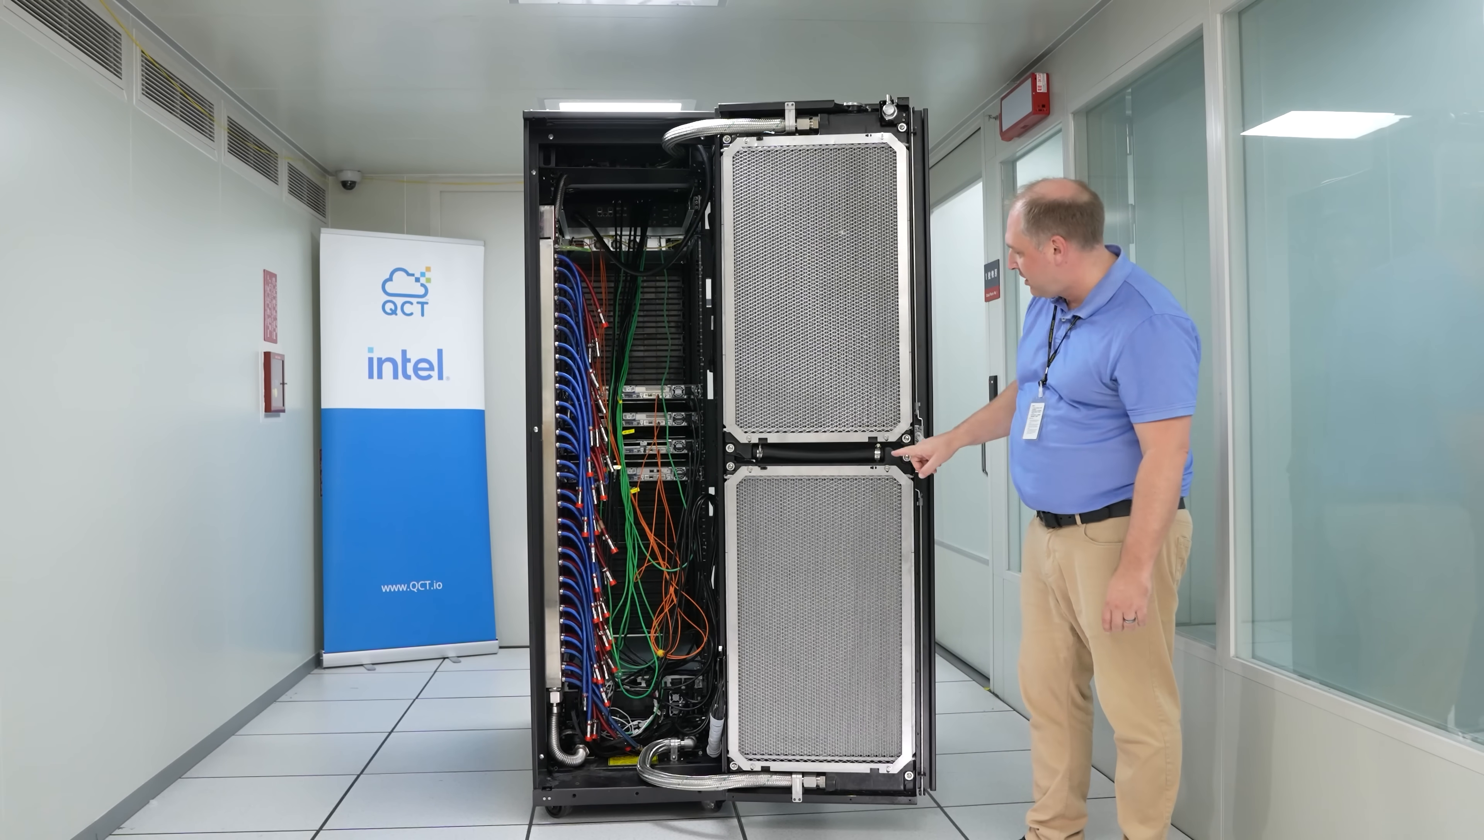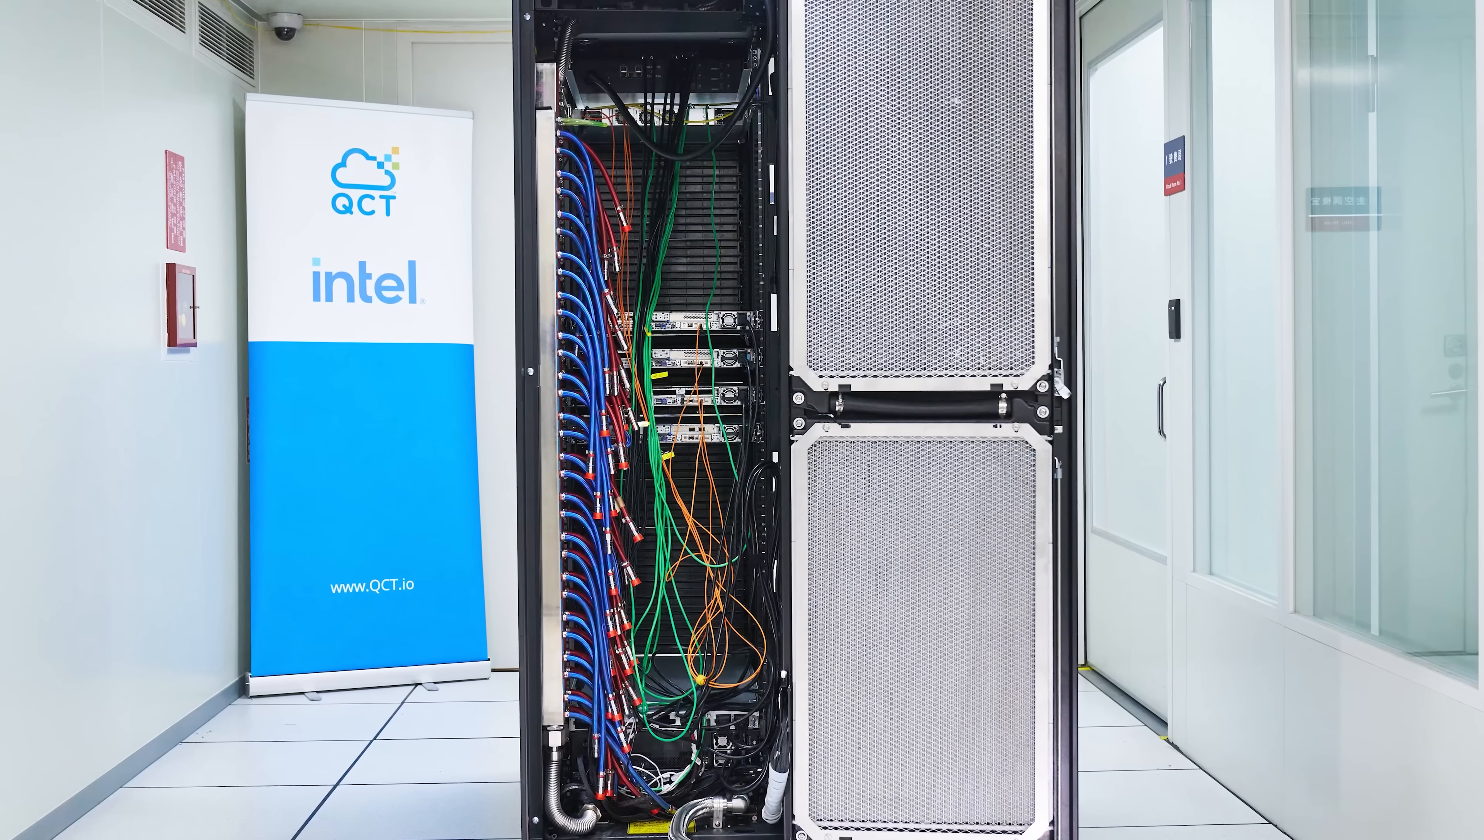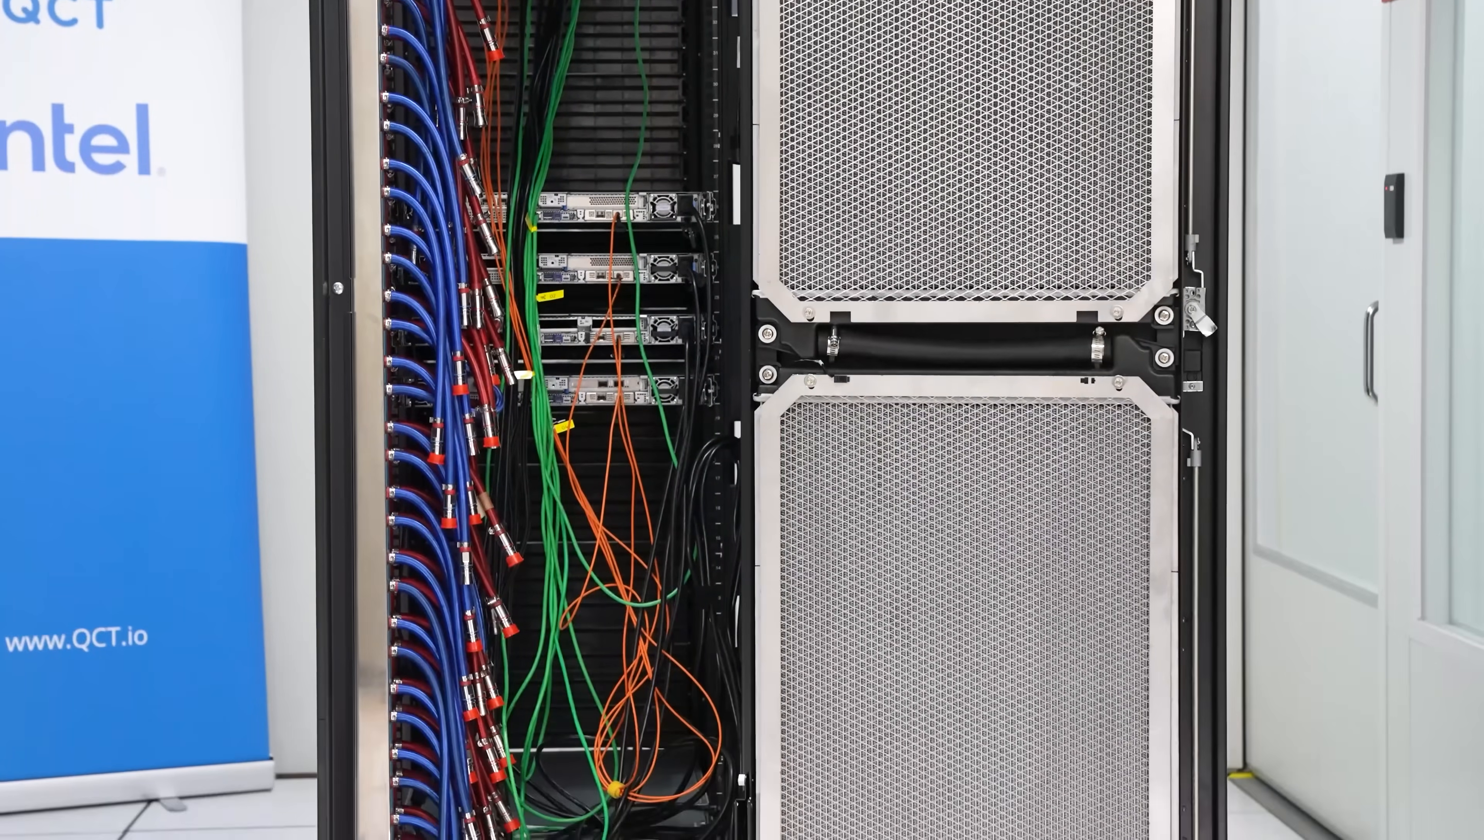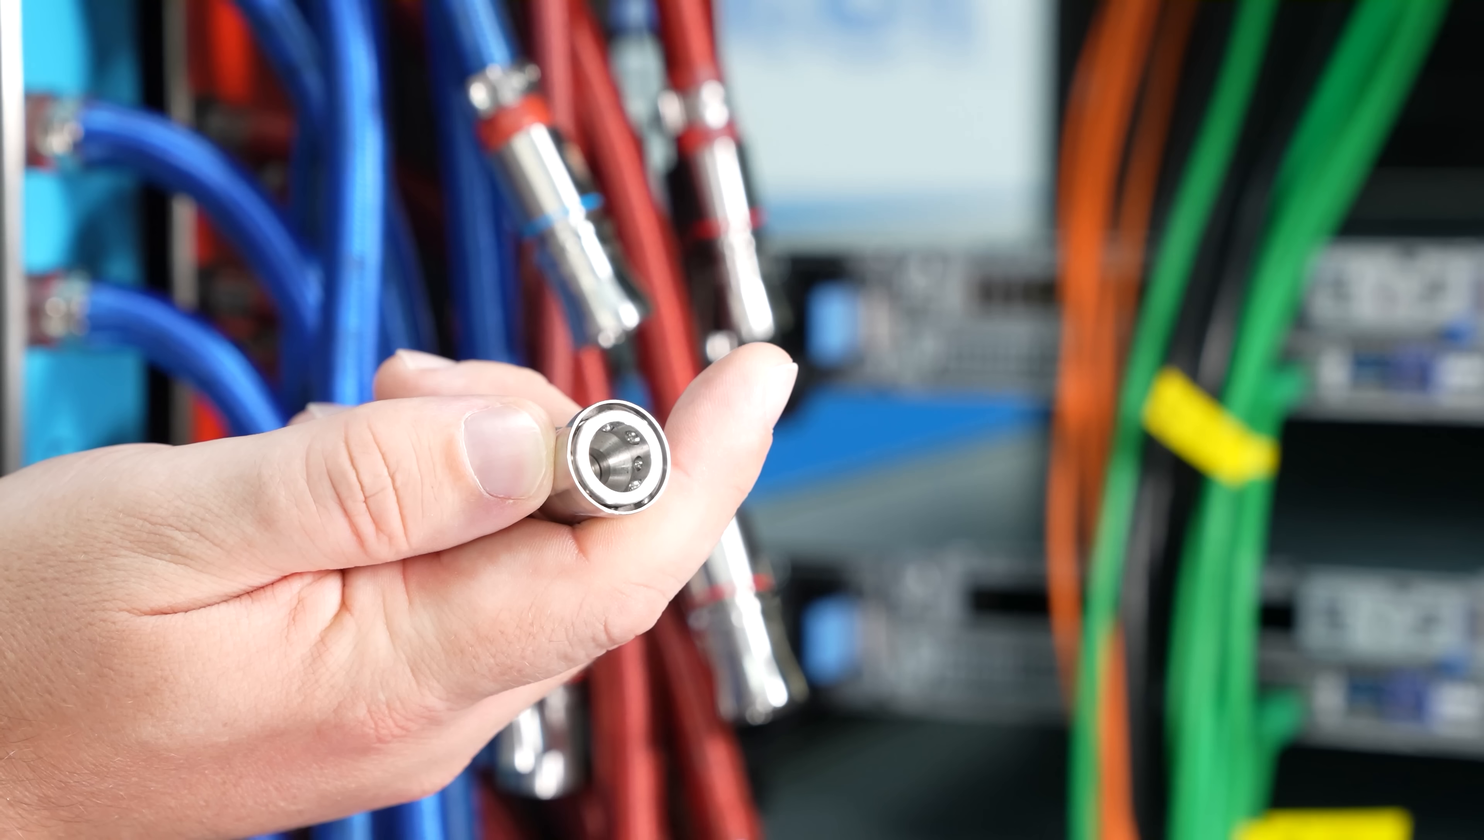Instead, you just are removing heat more efficiently from these 1U servers, and then you're using larger, more efficient fans and the radiator, so you have a just kind of more efficient setup, and you're able to move heat out of the chassis and out of the rack more efficiently. So the cool thing here is that it's all self-contained. Now, looking at the left side of the rack, you're going to see that we have our rack manifolds, and these manifolds are there, so that way you can take the cool liquid and distribute that into each individual server, and then you can take the warmed liquid out of each server and then bring it back to the CDU.